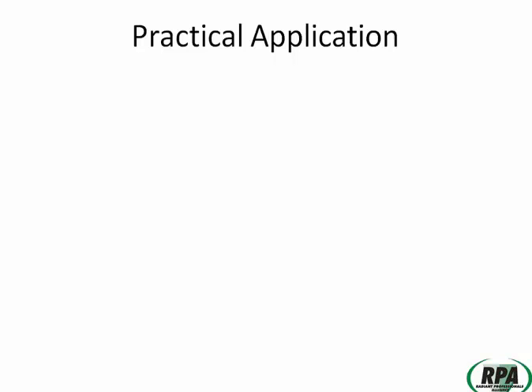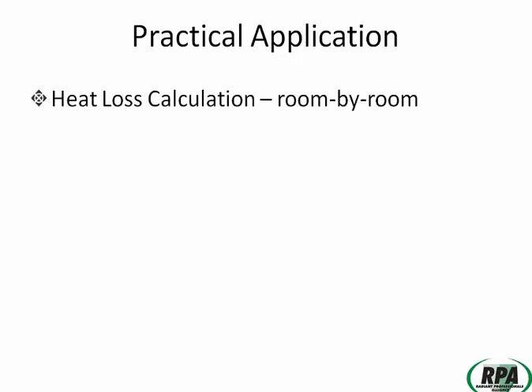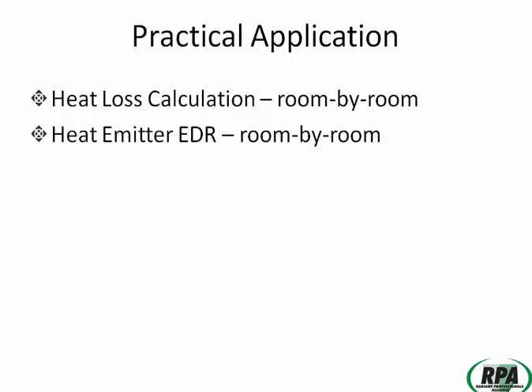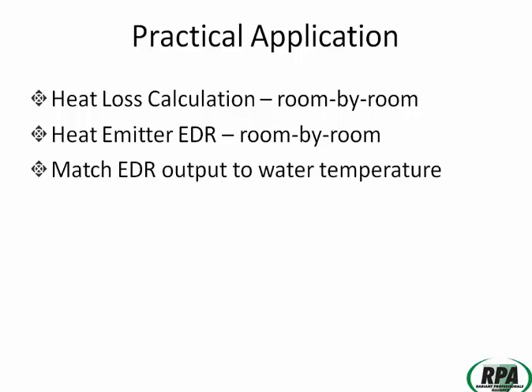Next slide, Mark. So we talk about the practical application of the heat loss calculation on a room-by-room basis. Go ahead and click, Mark. And heat emitters, equivalent direct radiation on a room-by-room basis. Go ahead, Mark. What we're trying to do is to match the EDR output temperature and use outdoor reset to its full advantage.